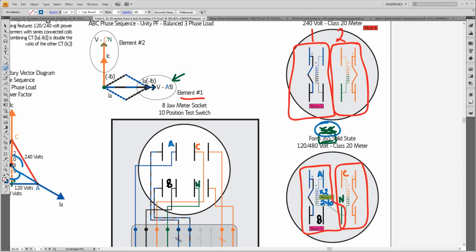This happened in probably 1992, I would guess, and I was visiting Cedar City, Utah, and they had changed theirs out supposedly, and we found one in the field that had been in the field since the early 90s with a billing error from the old 5S that they sold us at first. We got new meters replaced, the 35S for the 5S, and somehow it slid through the cracks, and there was a meter that had been sitting out for multiple years with 120 volts being metered with this current rather than the right meter at 240 volts metering that voltage with this current.